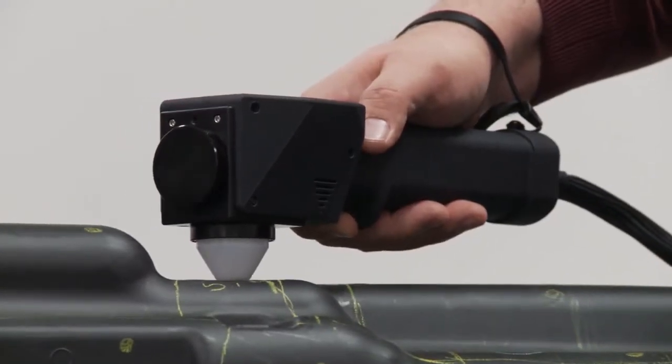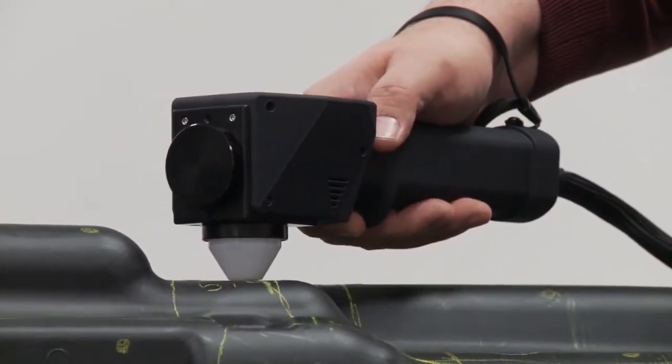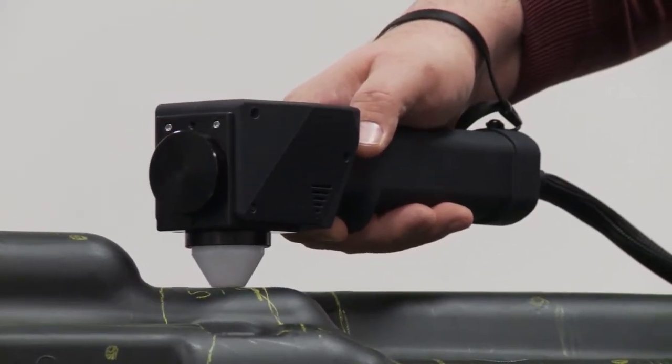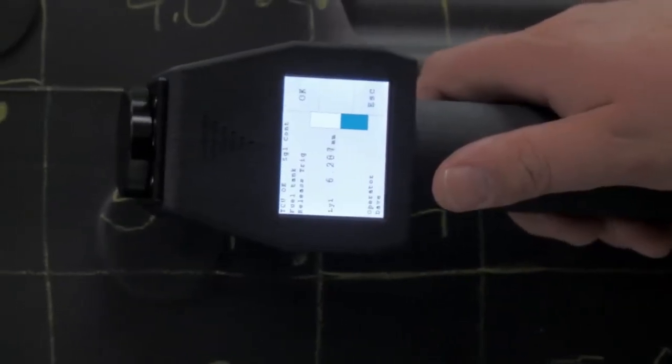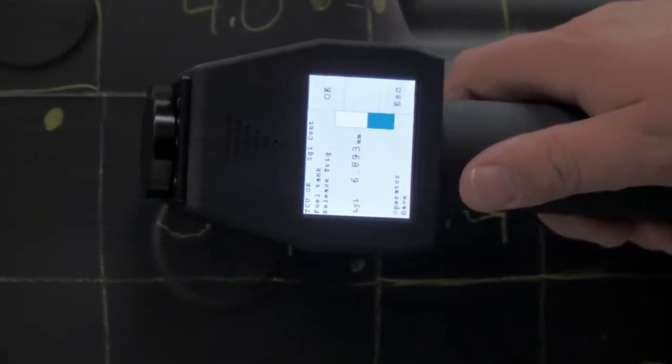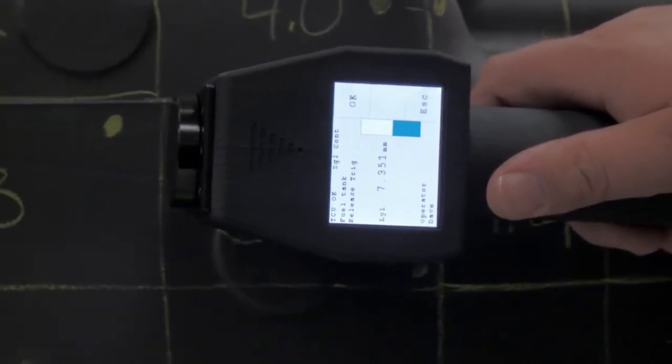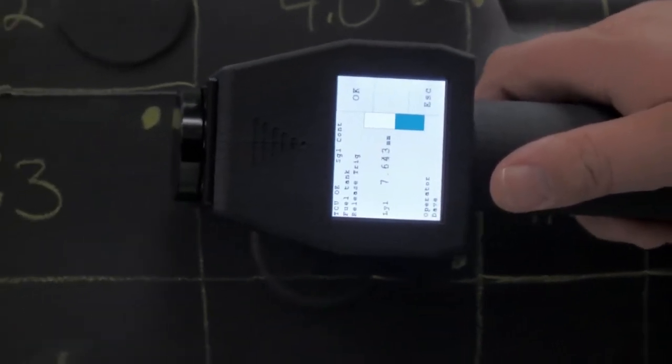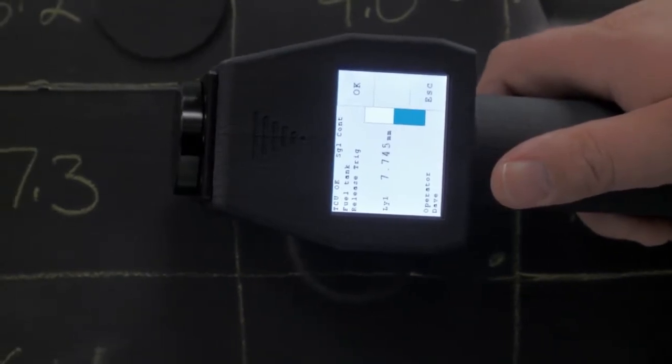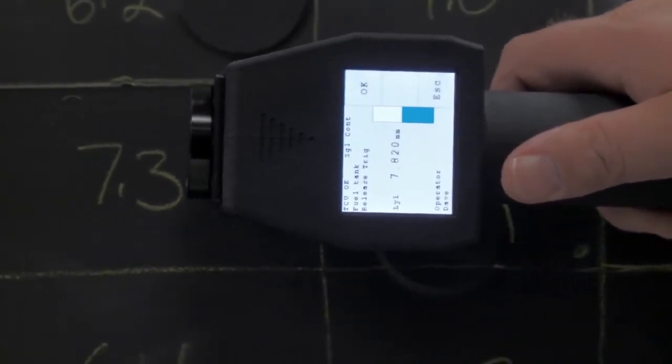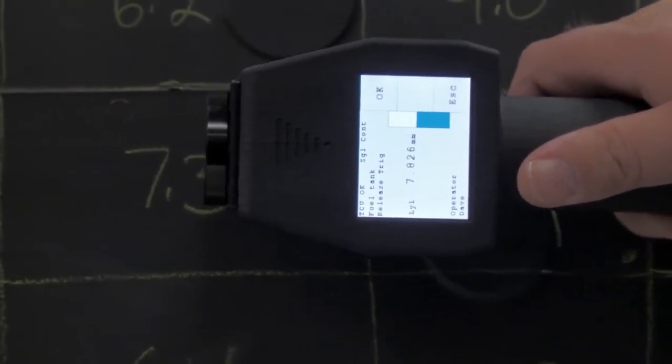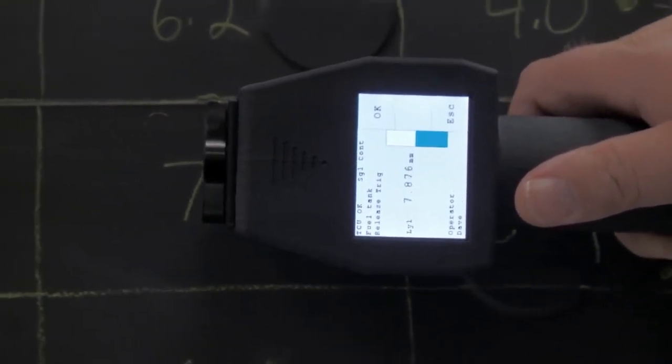A continuous tone related to the strength of the signal return can aid in maintaining proper alignment as the SPG is moved across the surface. The measurement starts when the trigger is pulled and is stopped when the trigger is released.